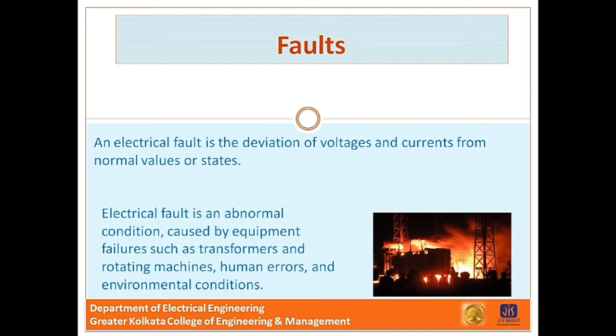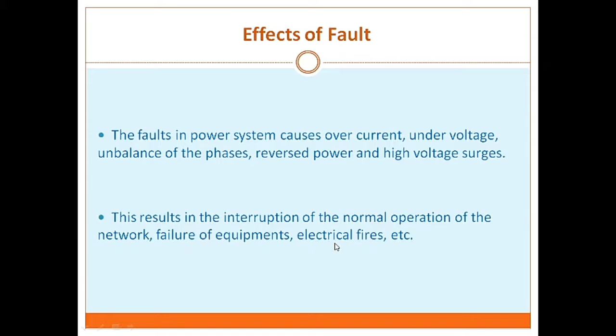Next one is the effects of fault. So what are the effects of fault? Usually the power system network is protected with switchgear protection equipment, to limit the loss of service due to electrical failures. Now, if electrical networks are subjected to a fault, the characteristic values of the machine such as impedance change. It also causes overcurrent, undervoltage, unbalance of phases, reversed power and high voltage surges in the system. This results in the interruption of the normal operation of the network, damages the equipment and causes electrical fires.